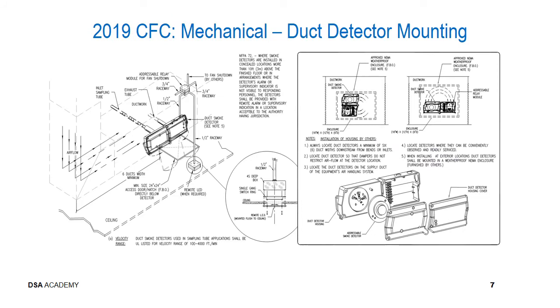Our next picture is that for the installation of the required automatic shutdown, generally achieved through installation of a duct-type smoke detector that must be installed in accordance with its listing and must be tied to the fire alarm system. It is important during installation that the inlet sampling tubes be installed in the correct orientation. This has often been found to be the reason for malfunctioning detectors or inoperative elements.